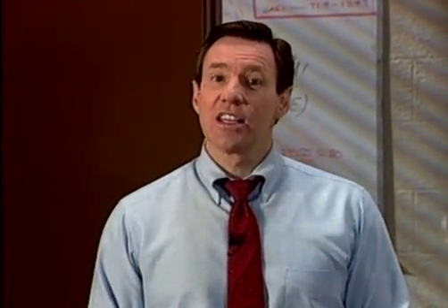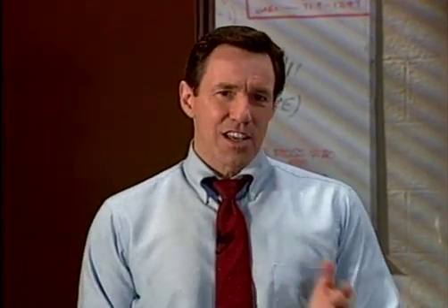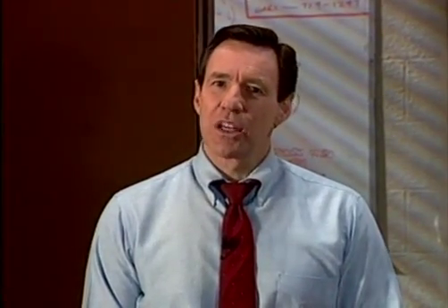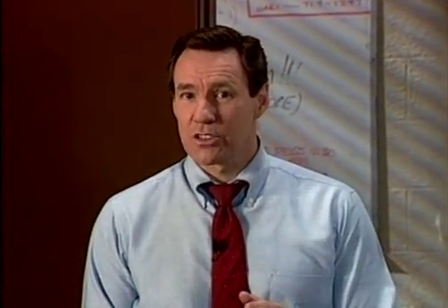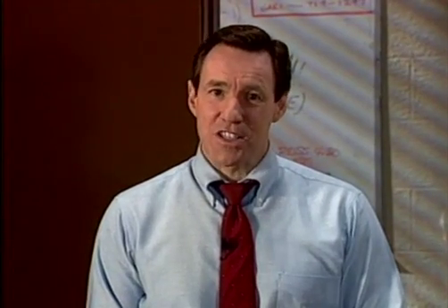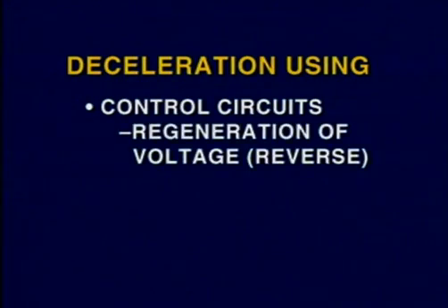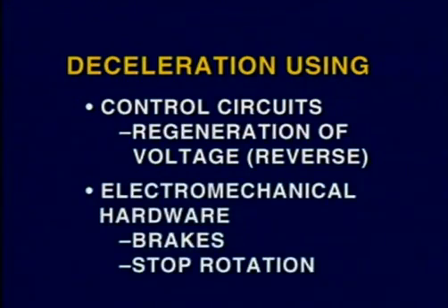Just as important as acceleration, if not more, are deceleration methods. Deceleration is used to bring a motor to a complete stop, and it uses control circuits or hardware components to accomplish this task. Control circuits provide electrical deceleration by causing regeneration of voltage in the reverse direction, while the electromechanical hardware, such as brakes, are used to bring rotation to a quick stop as soon as a motor is turned off.